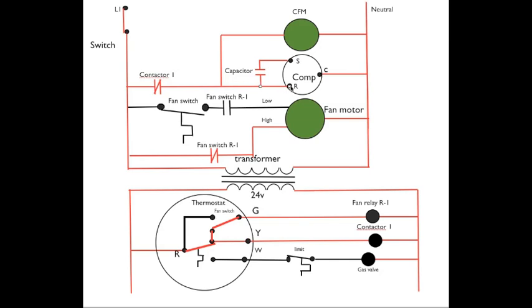Power goes over to run on the compressor, through the capacitor to start on the compressor, which starts the compressor. Power also passes up through here to energize the condenser fan motor.